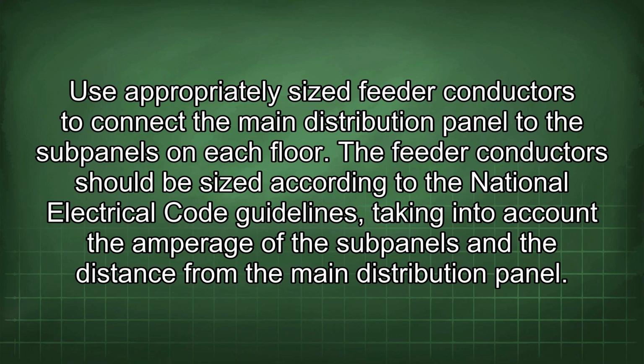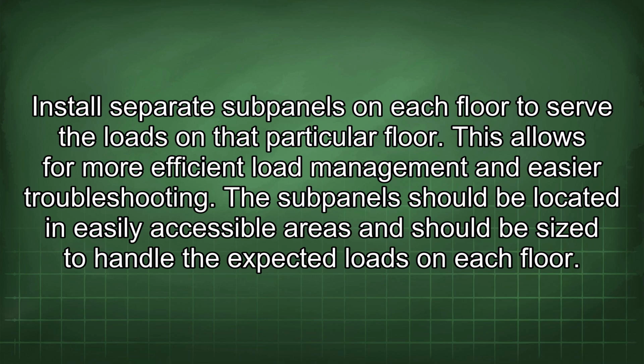The feeder conductors should be sized according to the National Electrical Code guidelines, taking into account the amperage of the subpanels and the distance from the main distribution panel. Install separate subpanels on each floor to serve the loads on that particular floor. This allows for more efficient load management and easier troubleshooting.